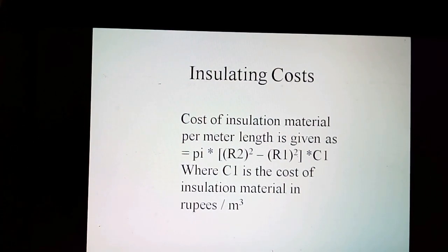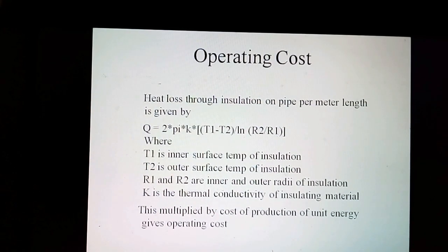Insulation costs: The cost of insulation material per meter length is given as C = π × (R2² − R1²) × C1, where C1 is the cost of insulation material in dollars per cubic meter. The cost of heat loss per meter length is equal to 2π × K × (T1 − T2) / ln(R2 / R1), where T1 is the inner surface temperature and T2 is the outer surface temperature of insulation, R1 and R2 are inner and outer radii, and K is the thermal conductivity. This is multiplied by the cost of production of thermal energy in operating costs.